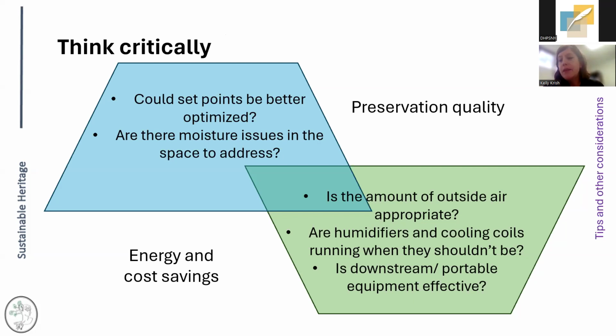From an energy standpoint, you can see how much outside air you're using compared to that moisture level. Maybe it's too much and it's causing the system to struggle, and that's why you're not able to maintain dehumidification in the summer. Are things operating the way that you think they would be, and effective and performing to the degree that you'd like?